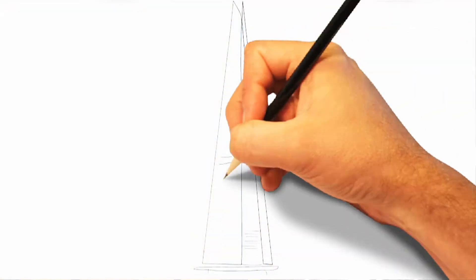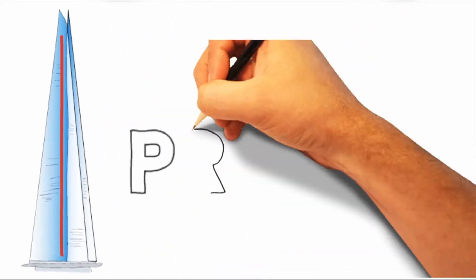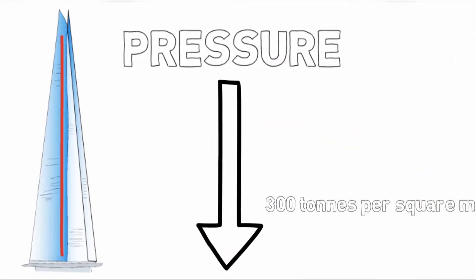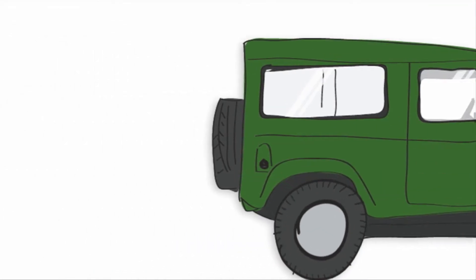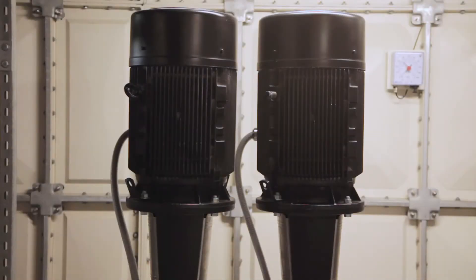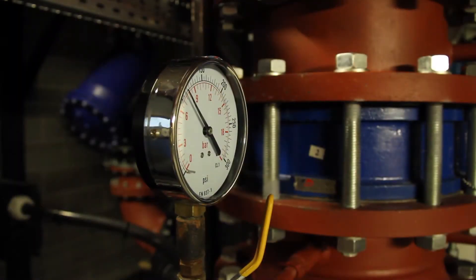So why have we put all these pumps and tanks in this building? Why not pump it directly from the basement all the way to the top of the Shard in one go? The answer is pressure. If a column of water stands in a single pipe from the top of this building to the bottom, due to the weight of the water, the pipe at the bottom must withstand a pressure of 300 tonnes per square metre — that's the equivalent of trying to hold a 4x4 in the palm of your hand. So my design includes tanks and pumps at various floors throughout the building which effectively break the pressure down into smaller amounts, keeping the pressures within the whole system down to levels found in your average height building.